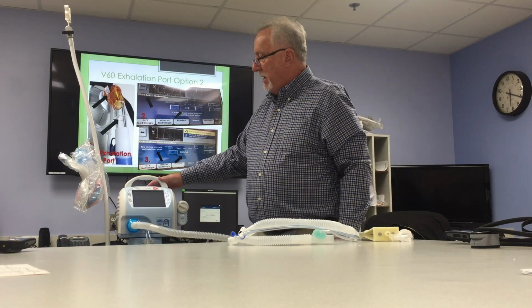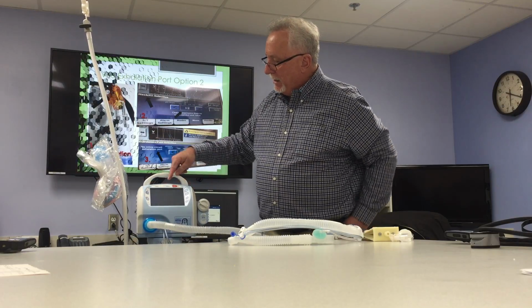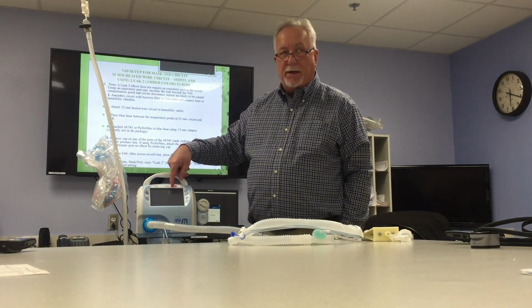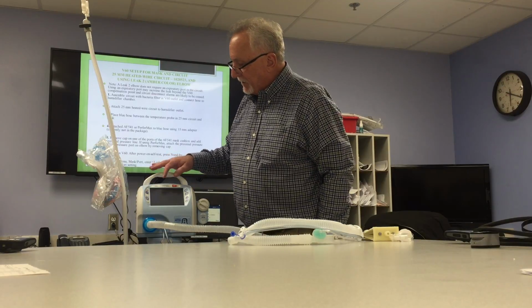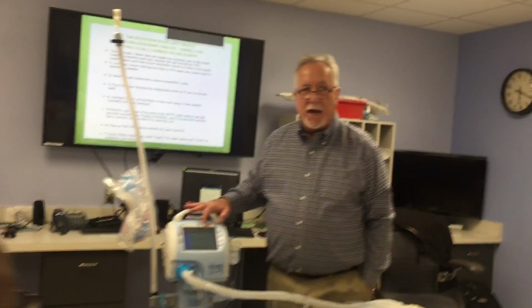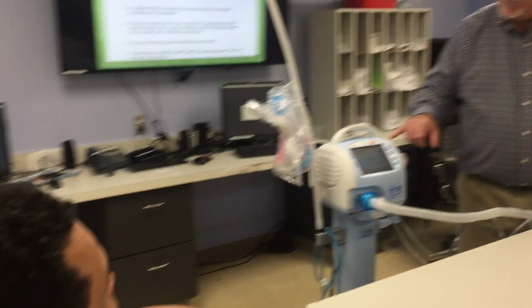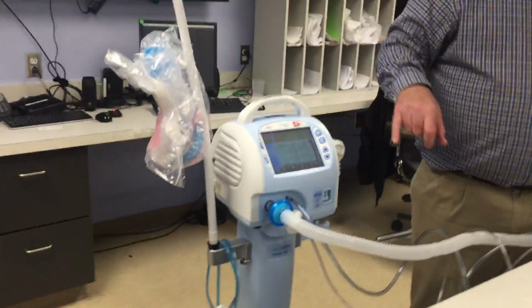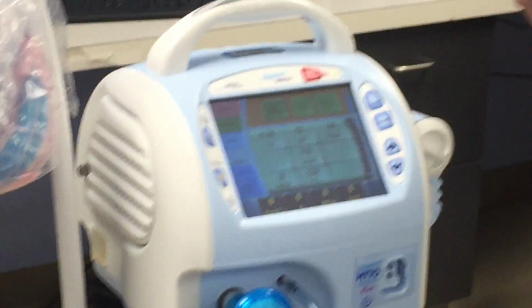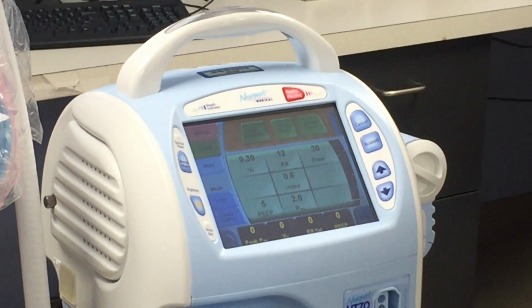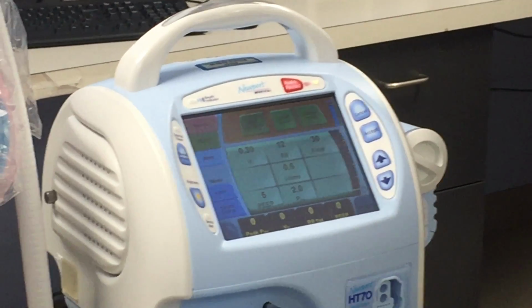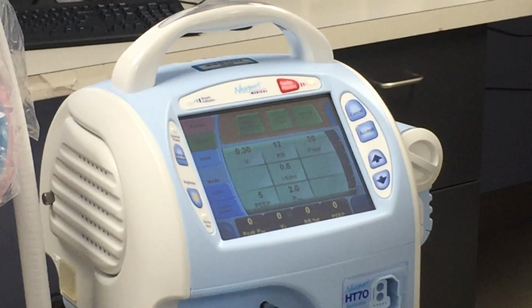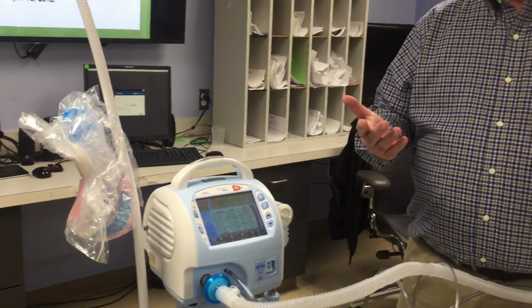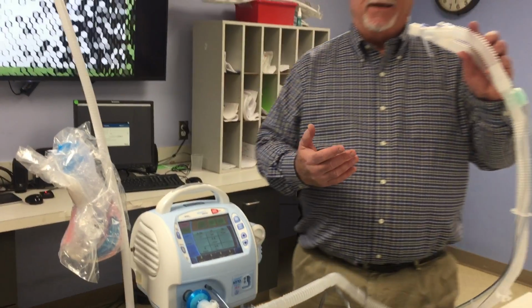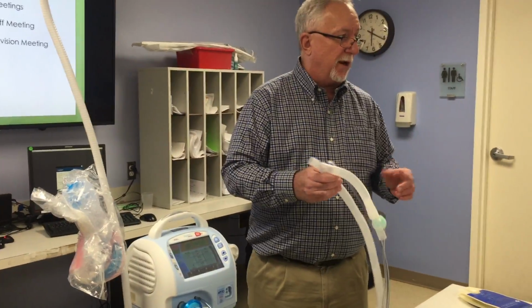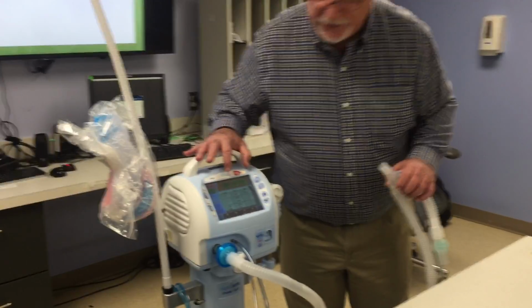And I'm just going to reset that. When you turn it on, you'll get 3 green buttons at the top here. One of them says start ventilation, circuit check. And the last one is custom presets. The one thing you have to do, especially if you're setting it up with a new circuit, just like you do on your ventilators now, when you put a circuit on there, what do you do? You do a circuit check. Pressurize the circuit, make sure you don't have any leaks, make sure everything's working correctly. And that's what you do with your circuit check.